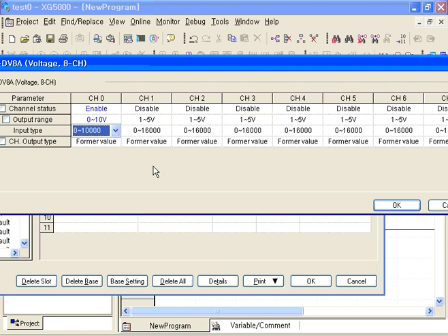And the next question. Input is very simple. Whatever happens in input, it does not affect the real output, because input means no instrument. Okay? Output is important. Output means something to be changed by controlling or applying some values. So output is important. This one, input, is just monitoring. So even the analog input module value is updated even when the PLC mode is stopped. You are able to do that. The module is updated, but analog output is important.